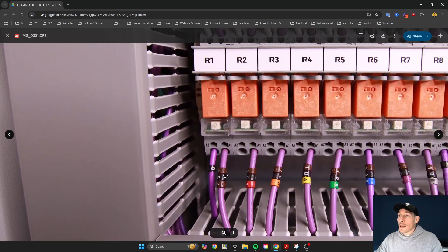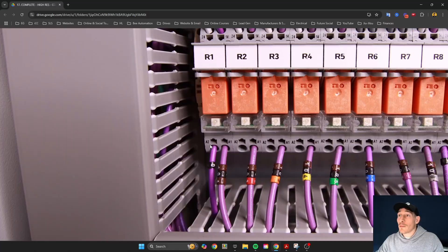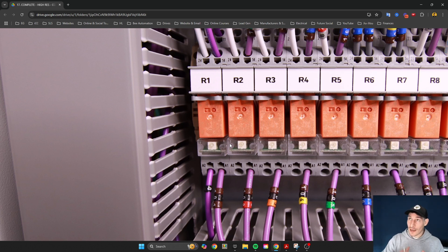You can see that this image I've got is exactly that relay we're looking at within the schematics — A2 here and A1 here. This is the coil side, which is what actually operates the relay and changes the contacts over. The cable feeding A1 is labeled 101, and the zero volts ground going from A2 is labeled 0, giving you a visual representation of how the schematic translates to the real world.